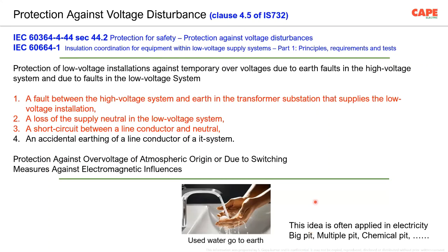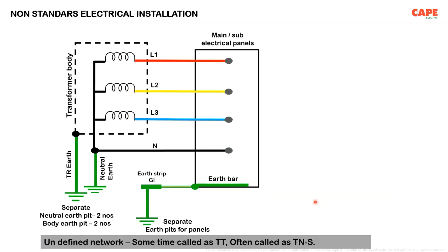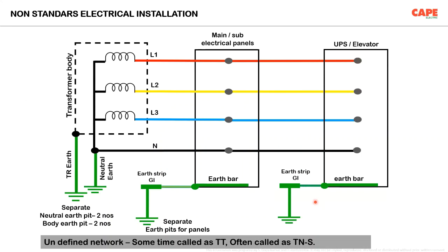One of the examples is, you know very well that in all my presentations, I always try to explain the transformer having a separate earth pit, the transformer neutral having a separate earth pit, two earth pits, the main distribution having two more earth pits, then the UPS, elevator, and the equipment have separate ones. Every part of the electrical installation is connected to a separate earth pit, and engineers try to make a bigger earth pit, chemical earth pit, and so on.